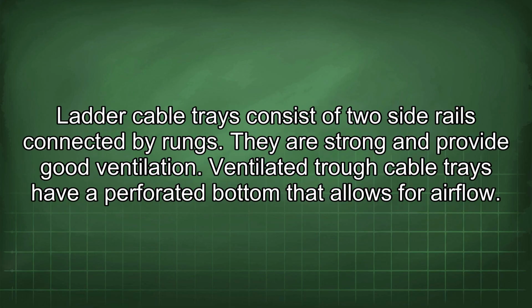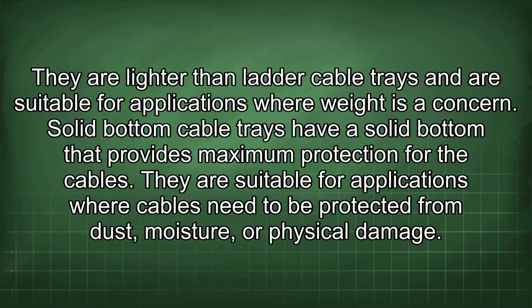There are several types of cable trays and wireways available. Ladder cable trays consist of two side rails connected by rungs. They are strong and provide good ventilation. Ventilated trough cable trays have a perforated bottom that allows for airflow. They are lighter than ladder cable trays and are suitable for applications where weight is a concern. Solid bottom cable trays have a solid bottom that provides maximum protection for the cables. They are suitable for applications where cables need to be protected from dust, moisture, or physical damage.